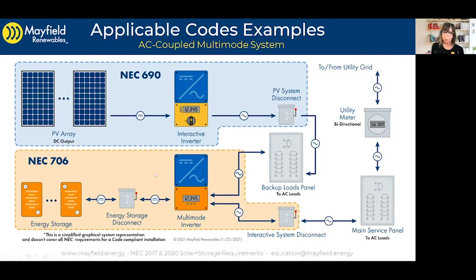Then we have our circuit sizing. We have different circuits here — we have input circuits. If we have a battery bank that is separate from our multimode inverter, we have to size those circuits between the battery bank and the disconnect, and between the energy storage disconnect and the multimode inverter. We have to make sure we're using the appropriate current on the input side of the inverter. And on the output side, we have a rated output that we'll use to size these AC circuits.